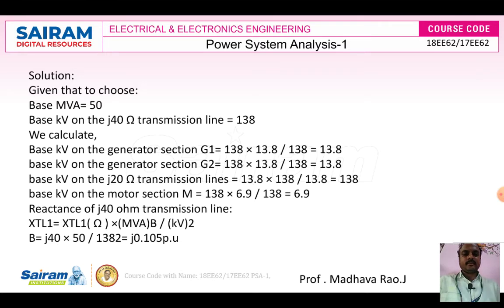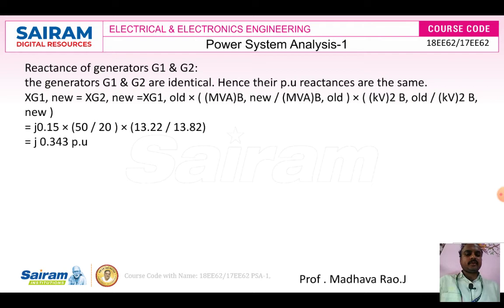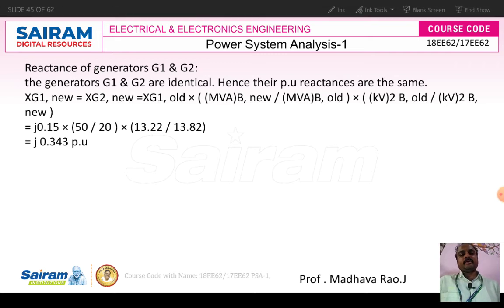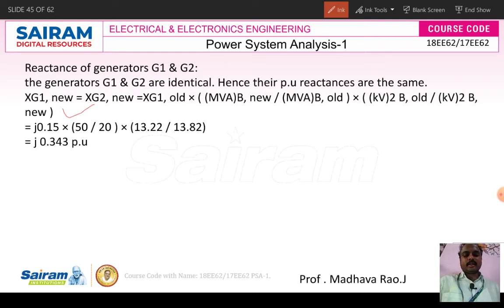For generators G1 and G2, since both ratings are the same, their new per-unit reactance values will also be the same. The standard formula is: new reactance = old reactance × (MVA_base_new / MVA_base_old) × (kV_base_old² / kV_base_new²). This same formula is used for transformers and motors as well.